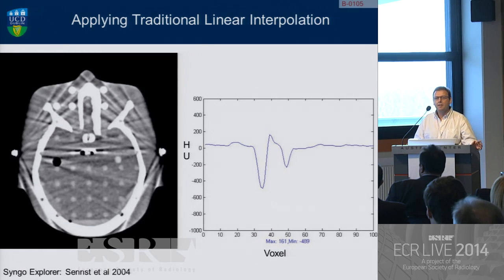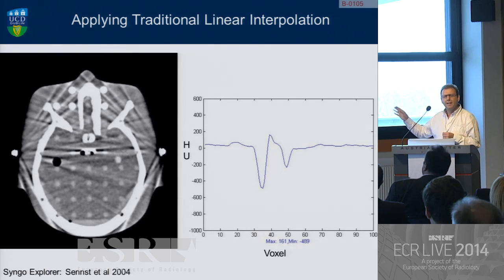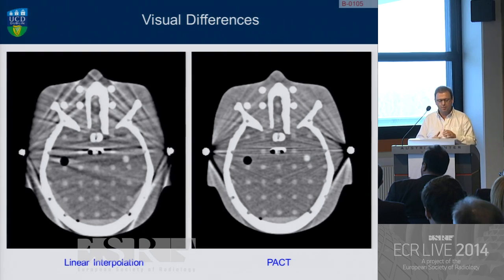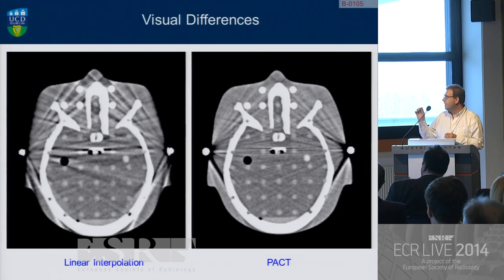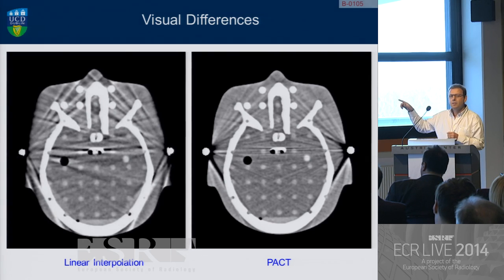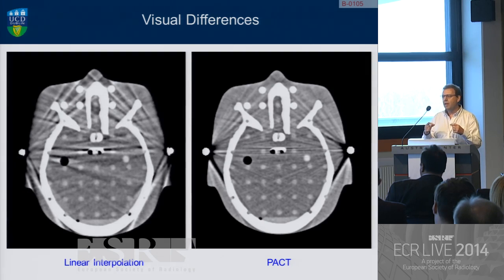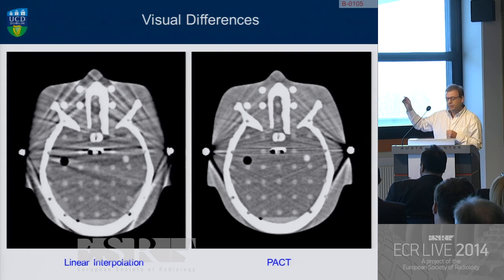If we apply a commercial metal artifact reduction routine — not iterative and not dual energy, this is conventional linear interpolation — we can see definite suppression of the artifact, but we can see some distortion in the voxel information. Applying the predictive artifact correction technique, we actually see good suppression of the primary artifact, and the pattern looks quite similar. Linear interpolation shows good suppression of the primary artifact visually, but we can actually see a worsening of other artifacts, particularly in the frontal or sinus area. This is because linear interpolation affects every single projection in the data set, as we're traveling through the sinogram and removing the entire metal data. Whereas the PACT algorithm only focuses on the overlap region, so we see good suppression of the primary streak but no influence whatsoever on the ancillary streaks or artifacts.